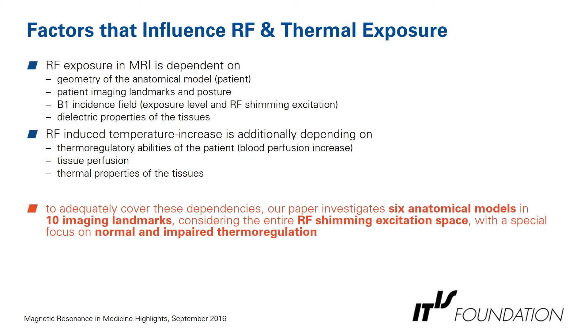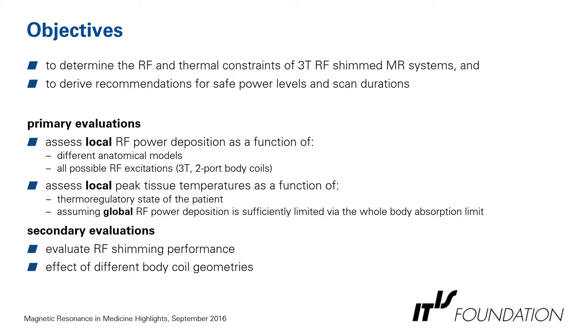Our paper investigates 6 anatomical models in 10 different imaging landmarks and considers the entire RF excitation space at 3 Tesla, with a special focus on normal and impaired thermoregulation. The overall objectives are primarily to determine the RF and thermal constraints of 3 Tesla RF-shimmed MR systems, and to derive recommendations for safe power levels and scan durations, including assessing local RF power deposition as a function of different anatomical models and all possible RF shimmed excitations.